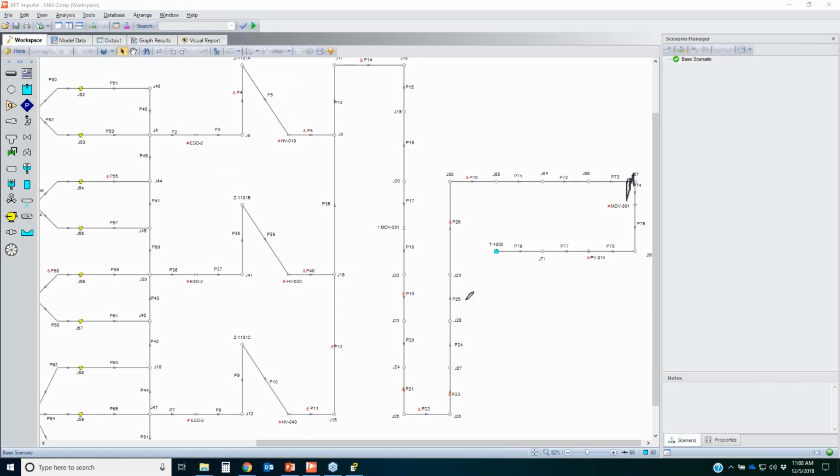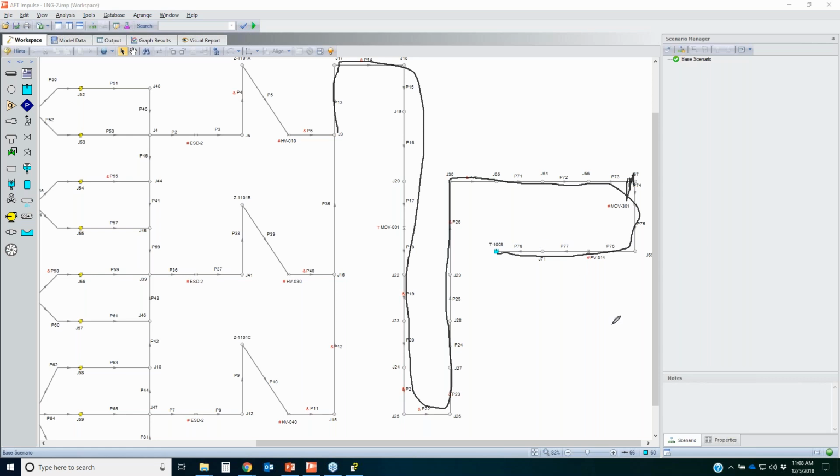You might want to do an animation. If you did an animation, you might select all the pipes in this continuous flow path, and you would use the animation capability to look at maybe both pressure and vapor volume, and you would see how the pressure and vapor volume in that flow path over length animates over time. You can zoom into these areas on that graph, and you can see when things start cavitating, and that will give you an indication of what's going on in your system.